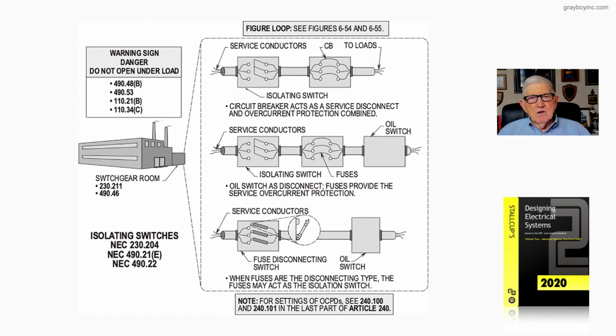Now, we've already talked about the warning signs: danger, high voltage, keep out. Danger, do not open under load, such as this isolation switch. Review 490.48(B), 490.53, 110.21(B), as well as 110.34(C). And this figure 17-4 is illustrating this concept of using an isolation switch to isolate the equipment that is being repaired, worked on, or serviced in some manner.